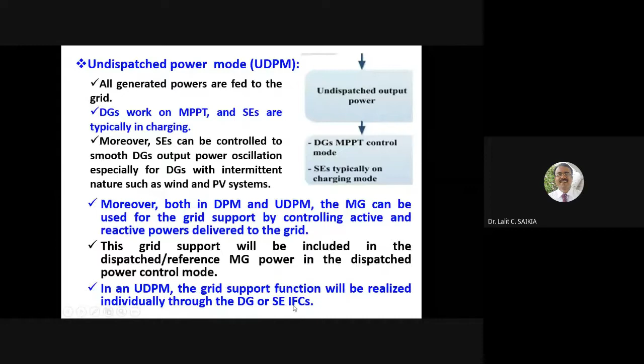Moreover, storage can be controlled to smooth the DG output power oscillations, especially for DGs with intermittent nature, such as wind and PV systems. However, in both dispatch and undispatched power modes, the microgrid can be used for grid support by controlling the active and reactive power delivered to the grid. This grid support will be included in the dispatch reference microgrid power in the dispatch power control mode. In the undispatched power control mode, the grid support function will be realized individually through the DG or SE interfacing converters, by controlling these.